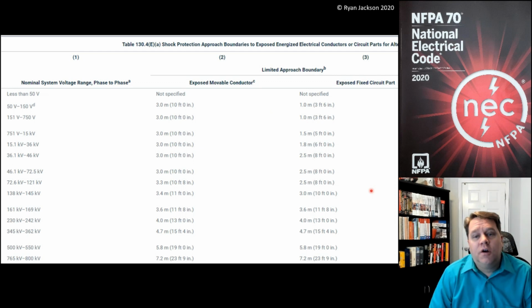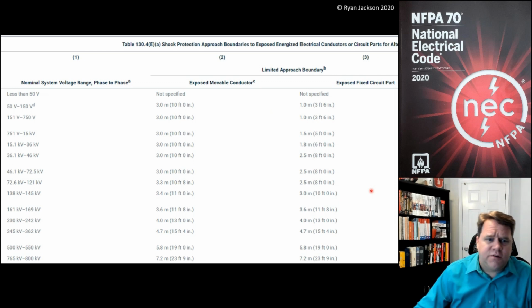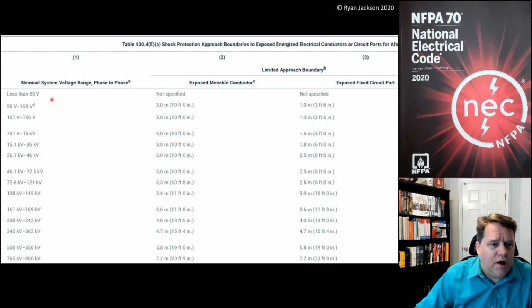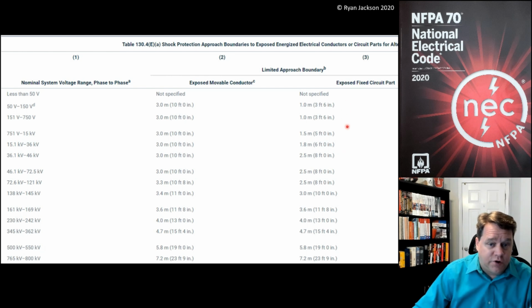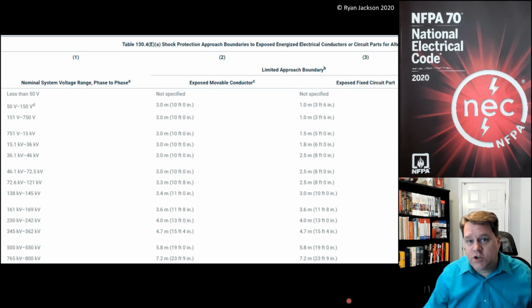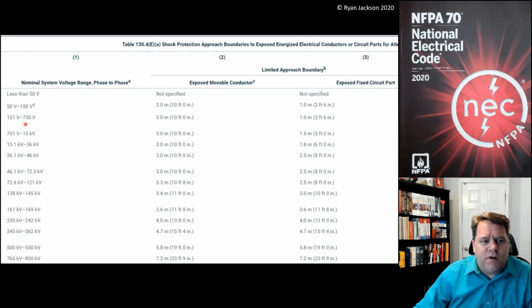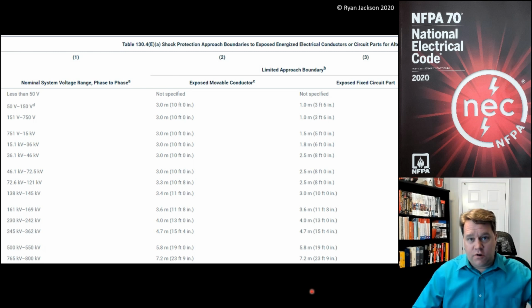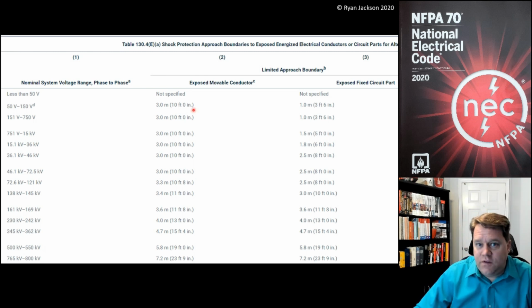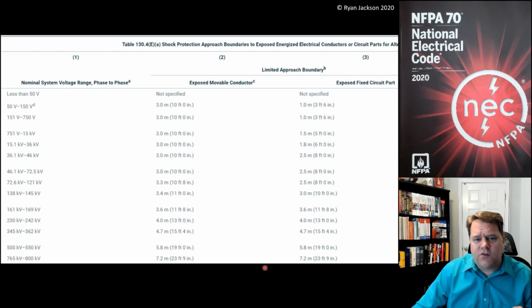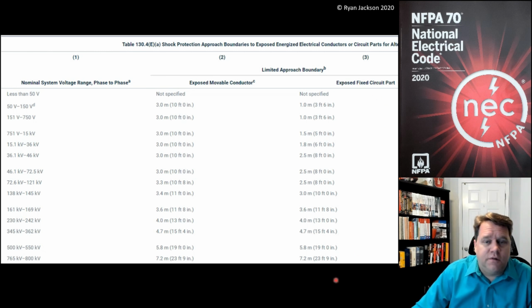And if you're not familiar with 70E, this is what it actually looks like. You can go down the voltage and measure to exposed fixed surface circuit parts, such as inside of a panelboard, switchboard, switchgear equipment. 50 to 750 volts is 3.5 feet. Now, to an exposed movable conductor, like a wire that's in the open air and can move around, well, then it's 10 feet. I don't think that issue comes up quite as often as a fixed circuit part, so we'll focus on the fixed circuit part for today's discussion.